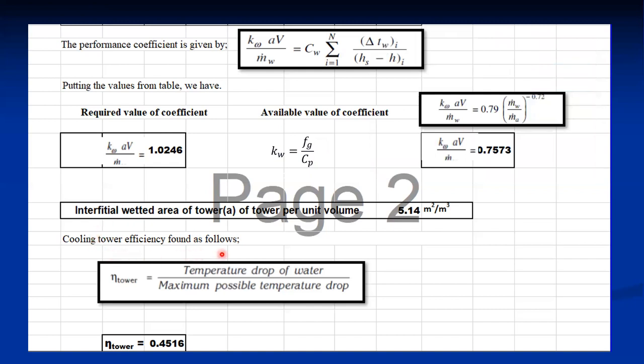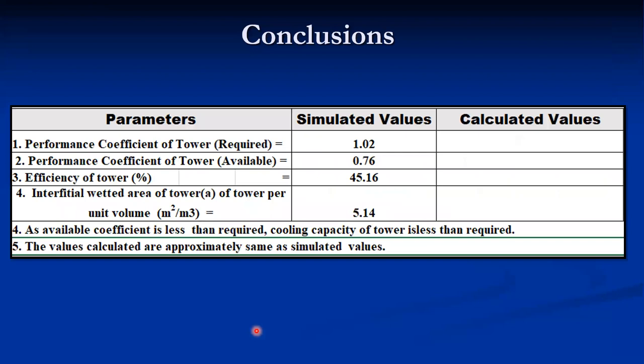The cooling tower efficiency is obtained using the formula: efficiency = actual temperature drop / maximum possible temperature drop. Actual temperature drop of water = inlet temperature − outlet temperature (already measured). Maximum possible temperature drop = inlet water temperature − WBT of entering air = 27°C. Putting all values in, the tower efficiency comes to approximately 0.45. The final results are: performance coefficient (required/demand value) = 1.02, and performance coefficient (available value) = 0.76.